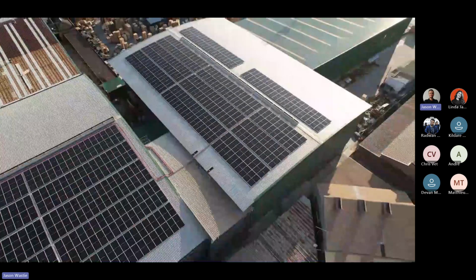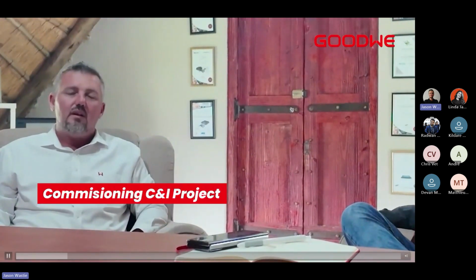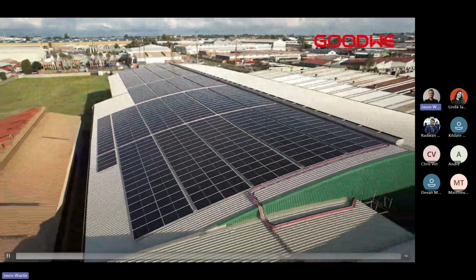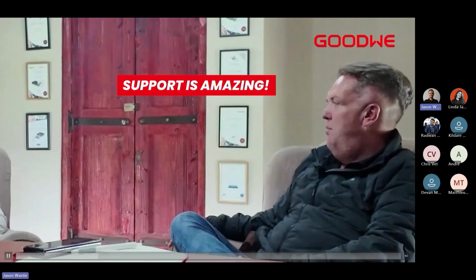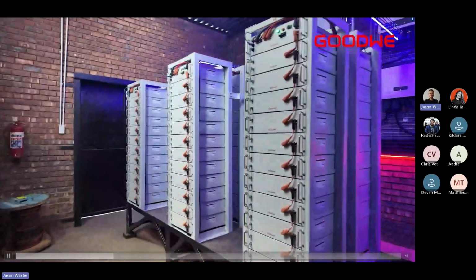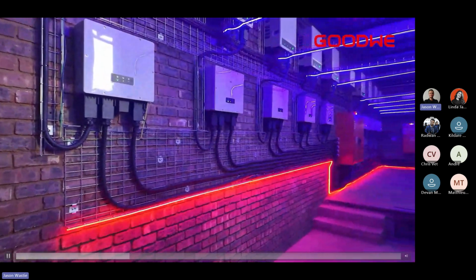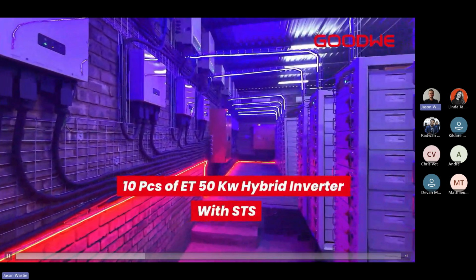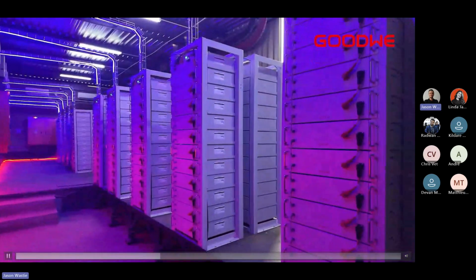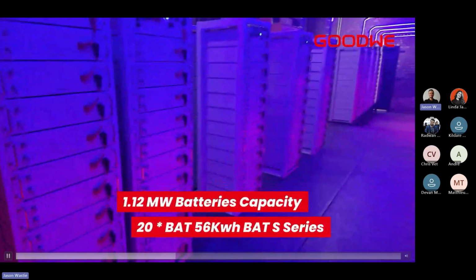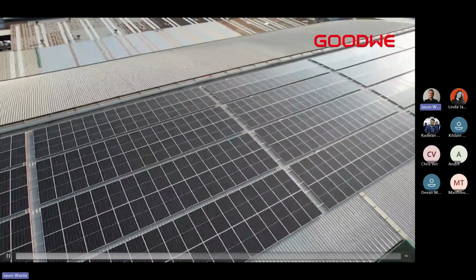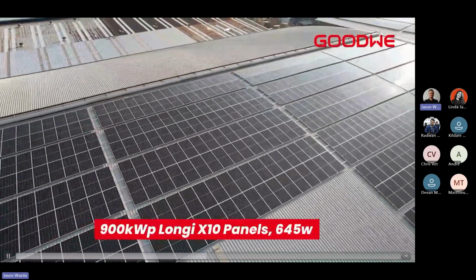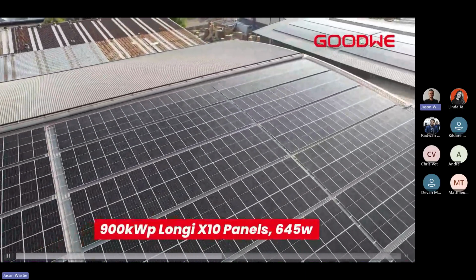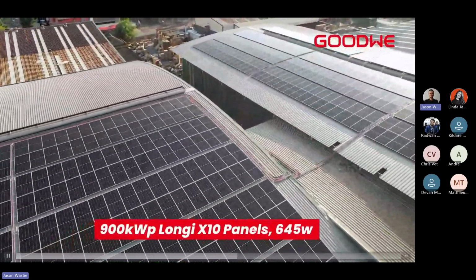Support is amazing. Been an absolute pleasure doing business with GoodWe. I'm here with Francois from Plexus, visiting a recently commissioned commercial storage project. Well, the reason why we prefer GoodWe is just, you know, the support is amazing, and fundamentally that's what we need. So we've got 10 GoodWe ET50 hybrid inverters with each of its own static transfer switch at the bottom. We've then got just over 1.1 megawatts worth of battery capacity deployed on the one site on the left. And then with just under a megawatt worth of PV production coming from the top. We specifically designed the project around the Longi X10 645 watt panel.